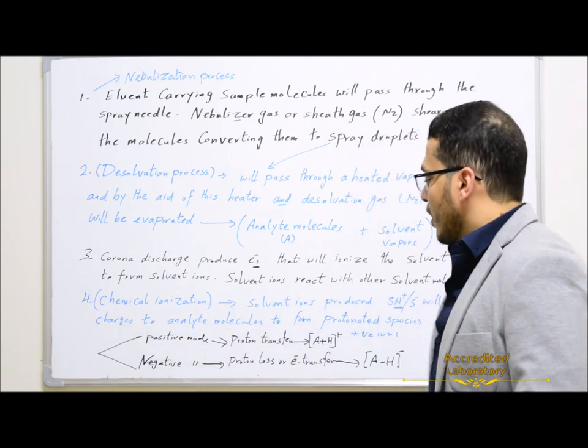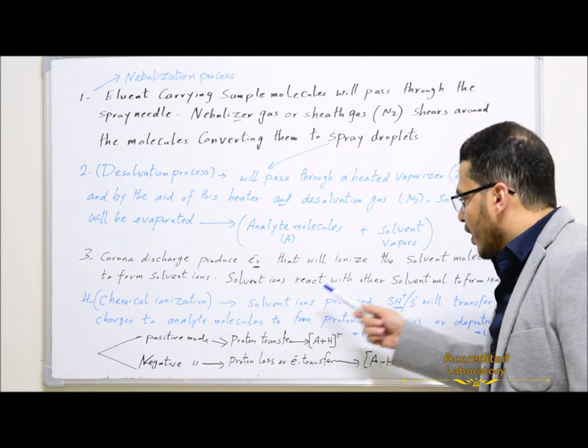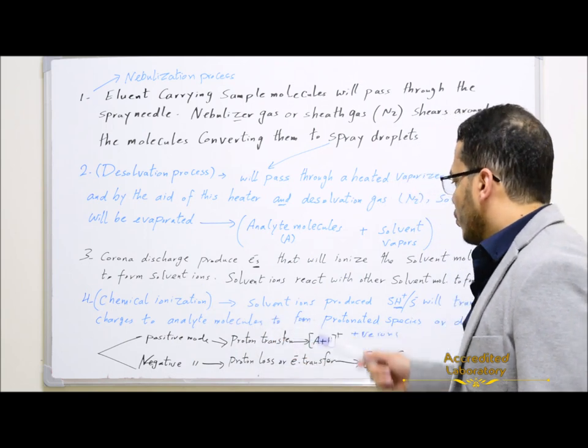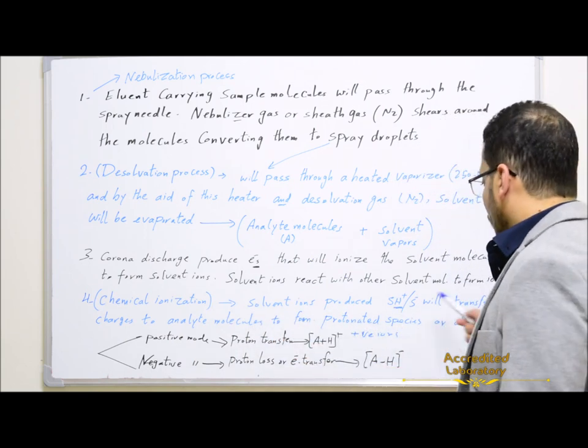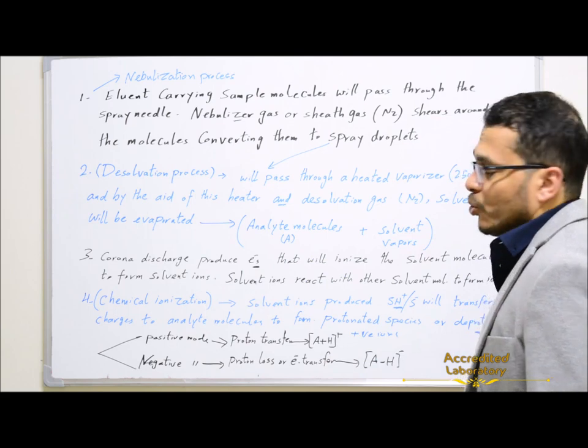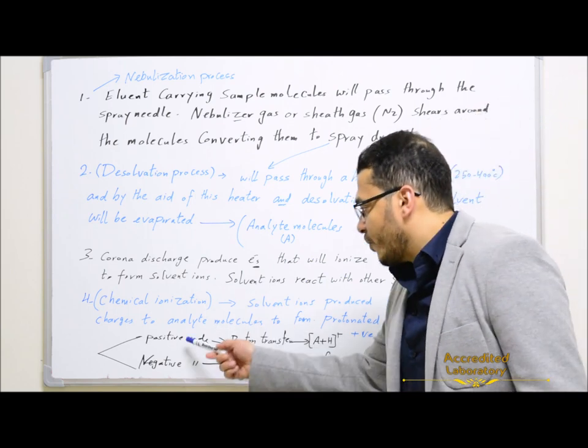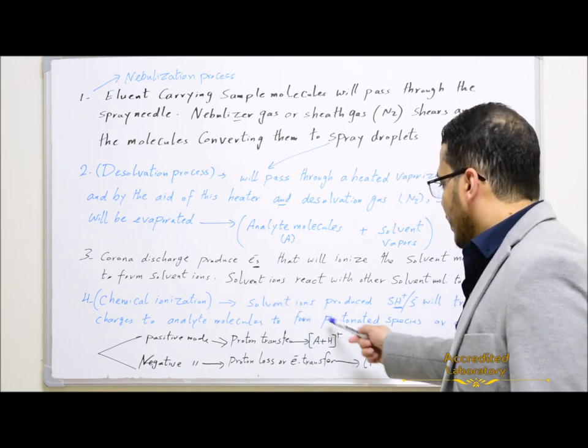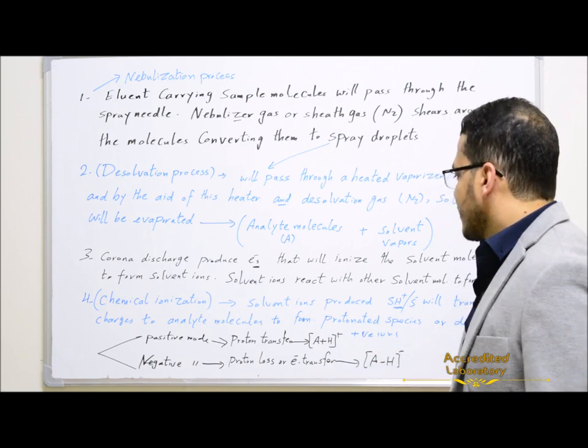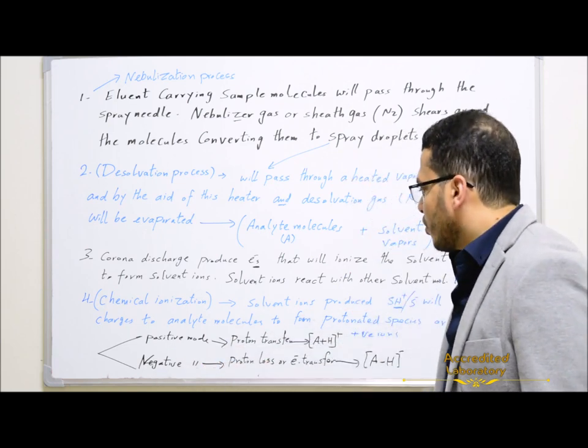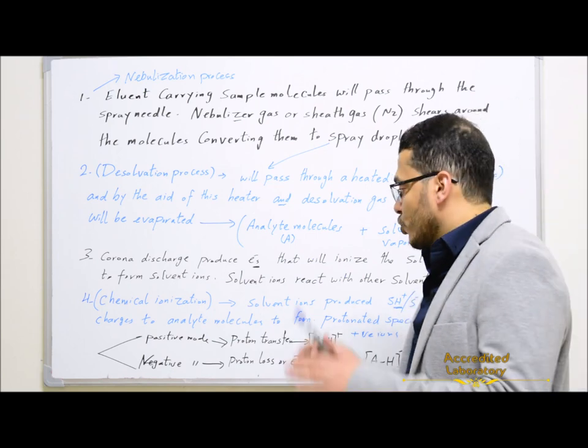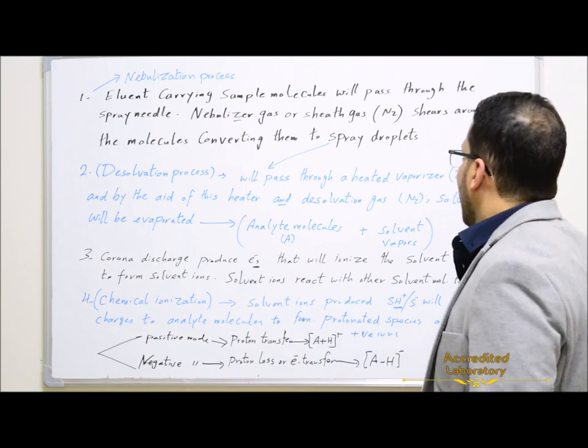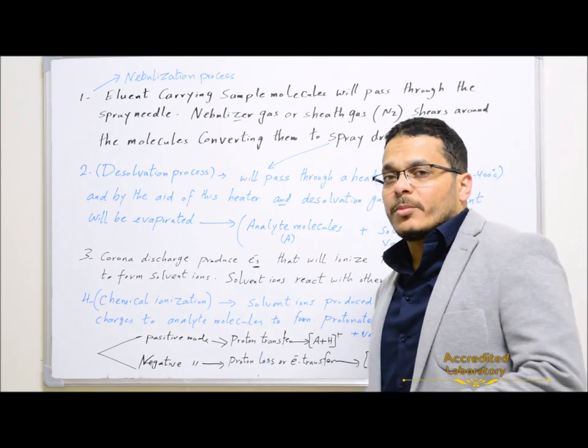At the end, chemical ionization for analyte molecules: solvent ions produced will transfer charges to analyte molecules to form protonated species — positive ions — or deprotonated species — negative ions. In case of positive mode, proton transfer occurs from solvent ions to analyte molecules. In case of negative mode, proton loss or electron transfer from solvent ions to analyte molecules forms analyte ions that will be transferred to the mass analyzer.